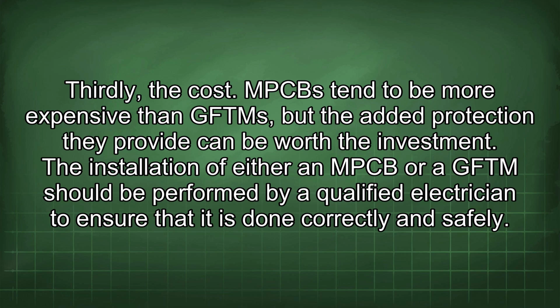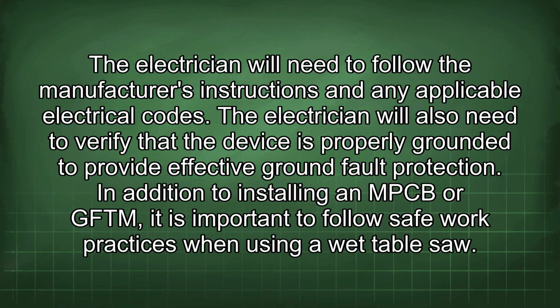The installation of either an MPCB or a GFTM should be performed by a qualified electrician to ensure that it is done correctly and safely. The electrician will need to follow the manufacturer's instructions and any applicable electrical codes. The electrician will also need to verify that the device is properly grounded to provide effective ground fault protection.